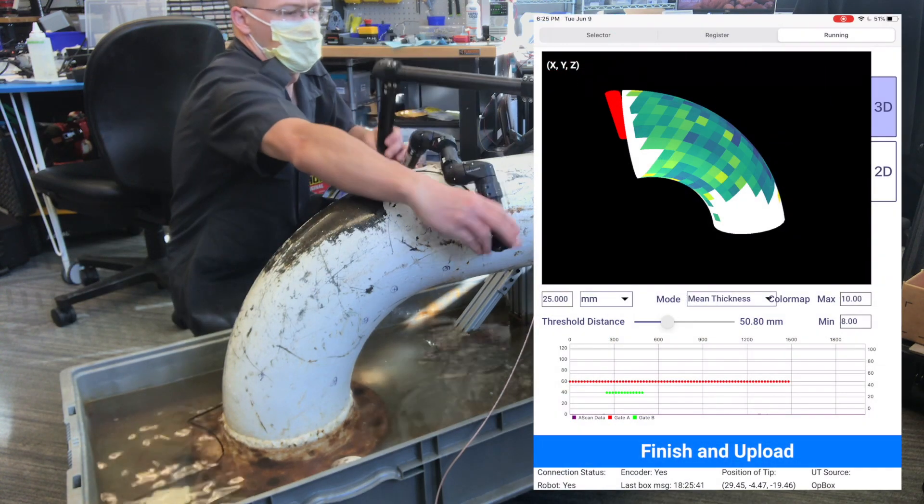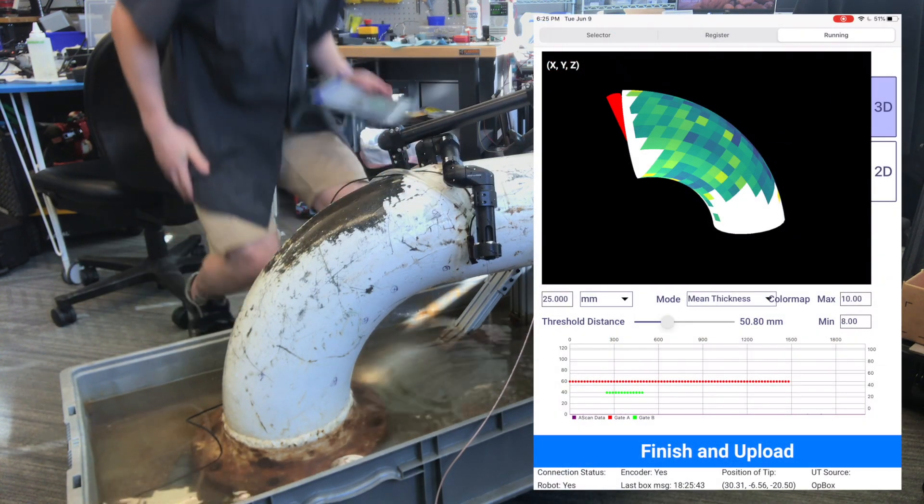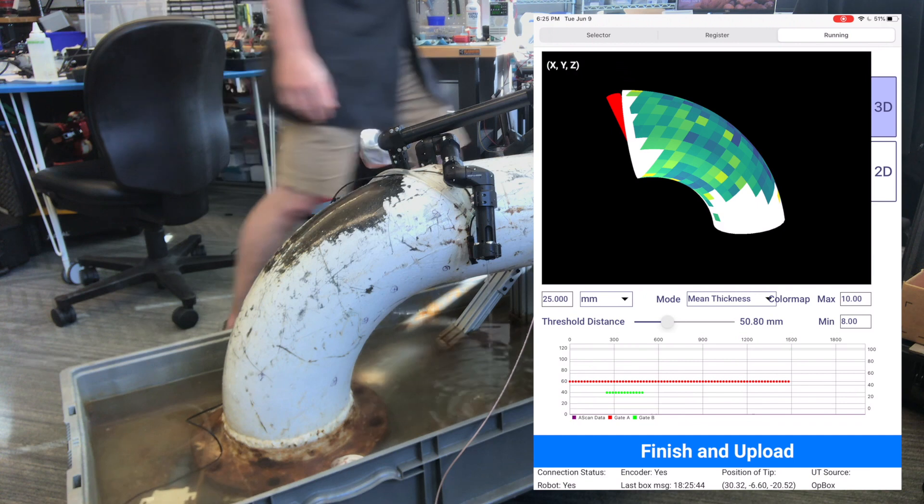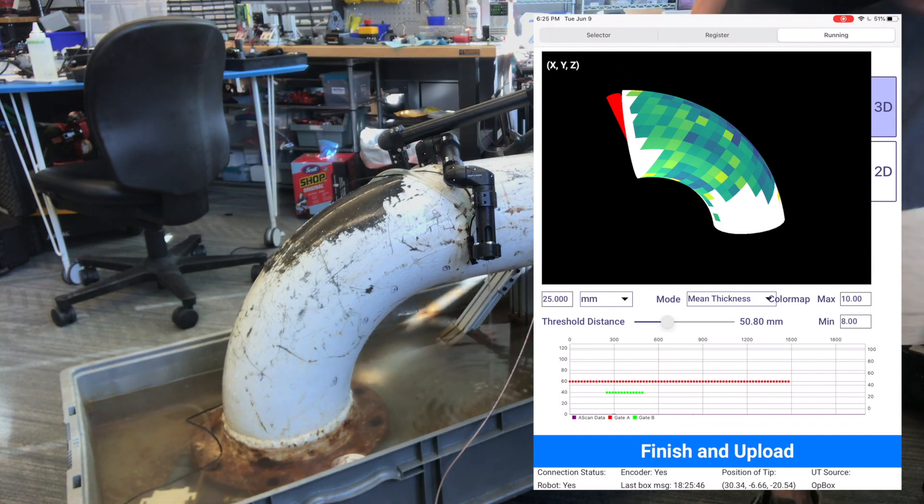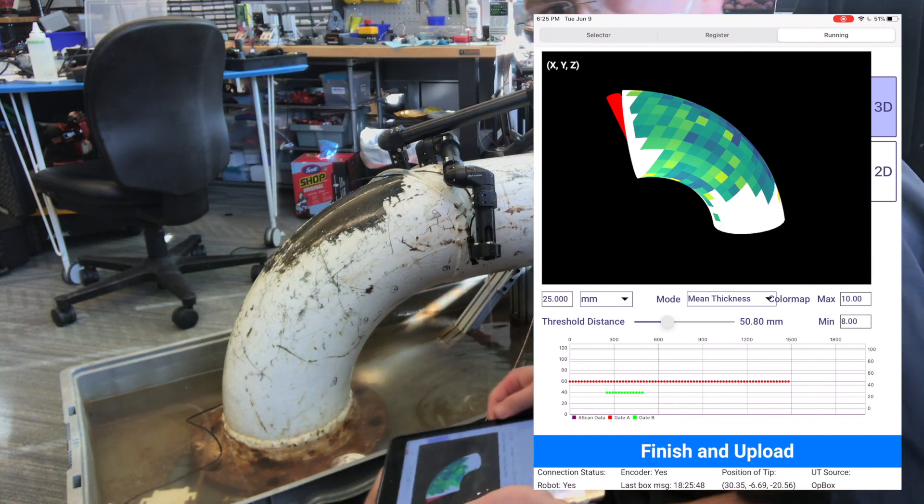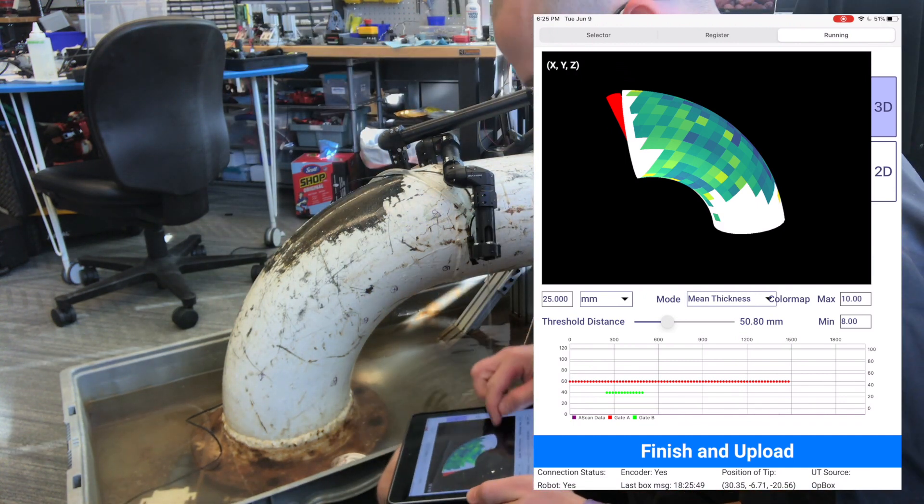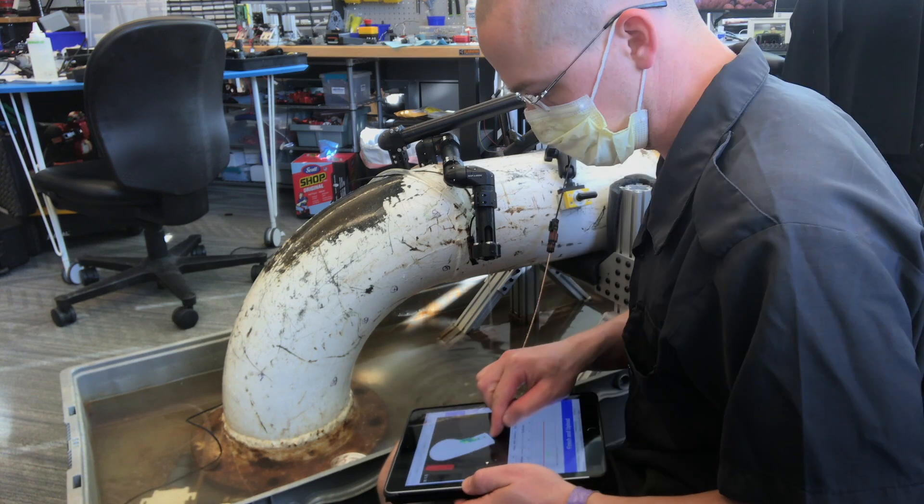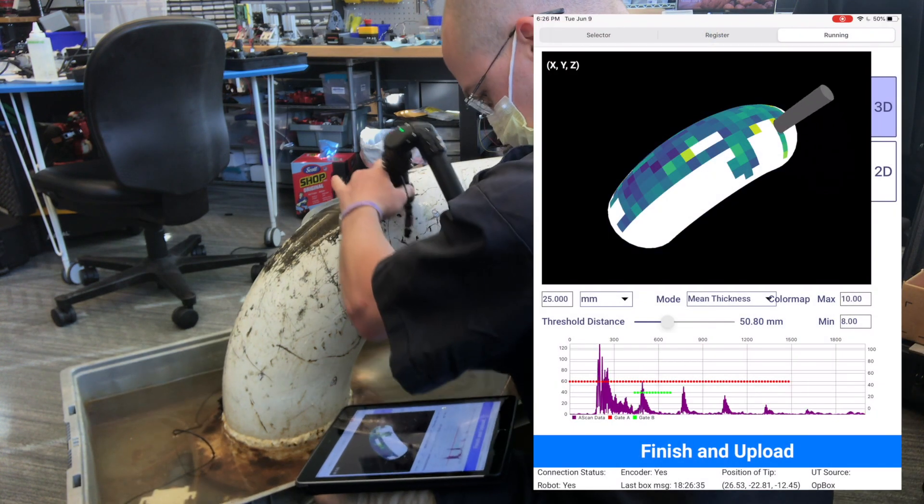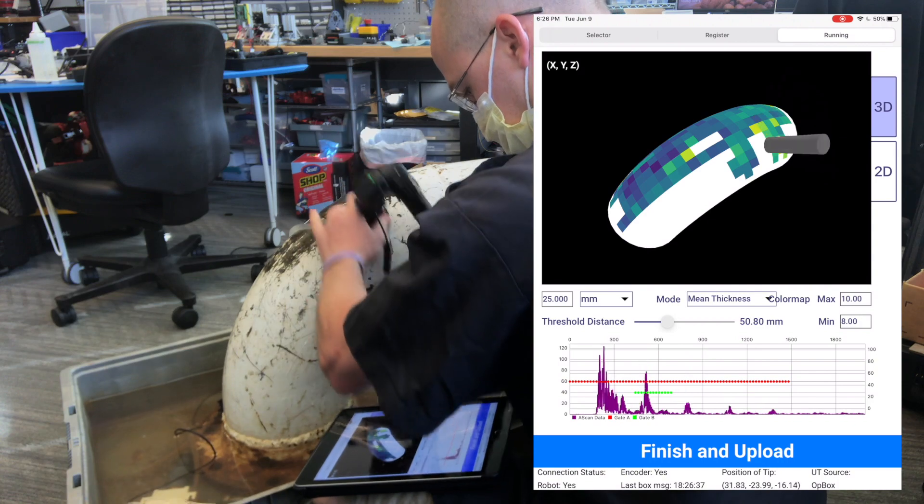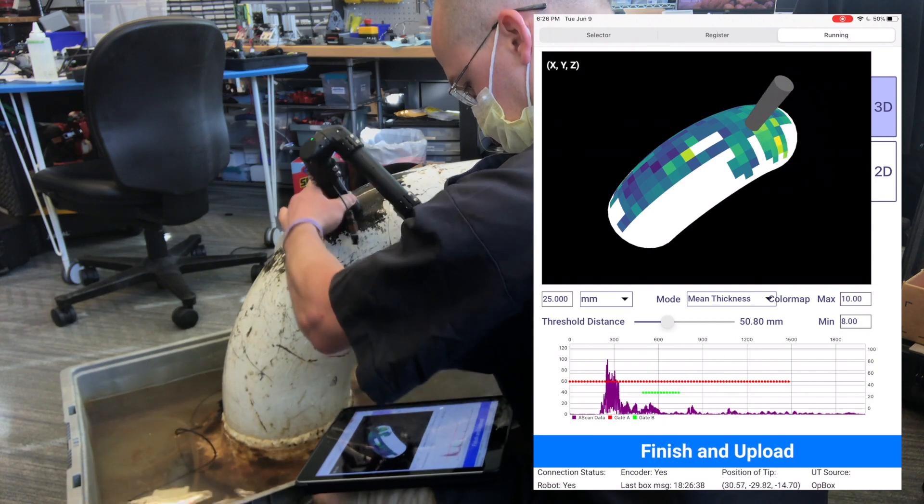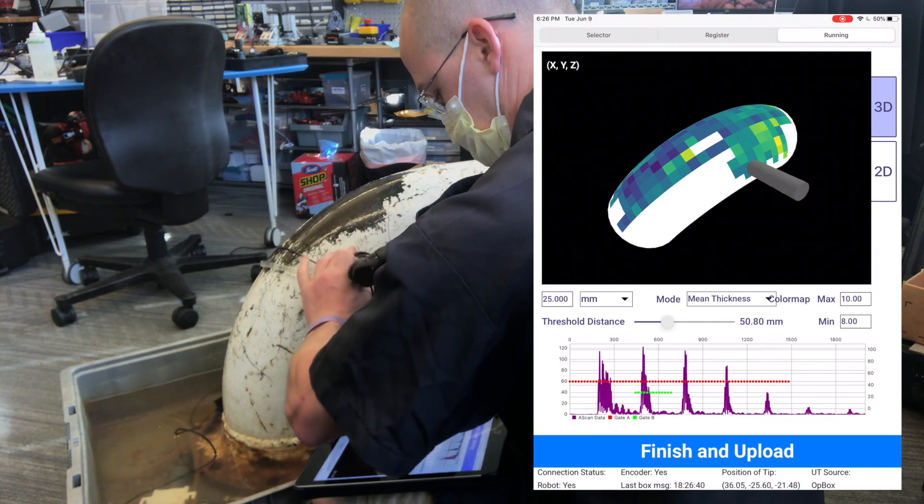Because you're always measuring the position of the probe live, and you know how close the probe is to the surface, the operator is free to inspect the surface any way that works. If they need to take a break and move around the surface, come back, and start scanning from a different side, MAPS can do that.